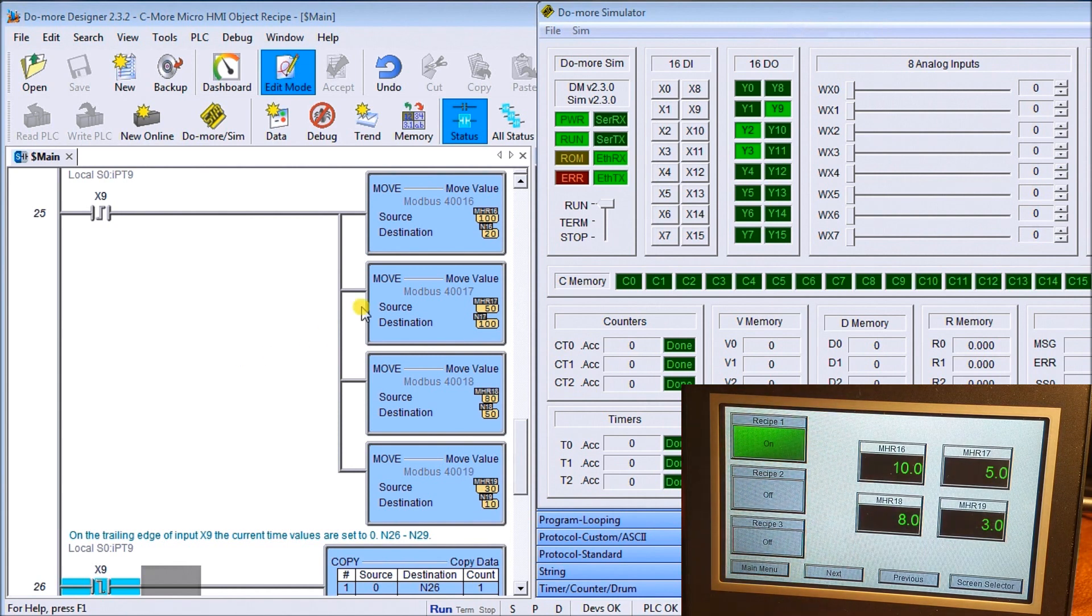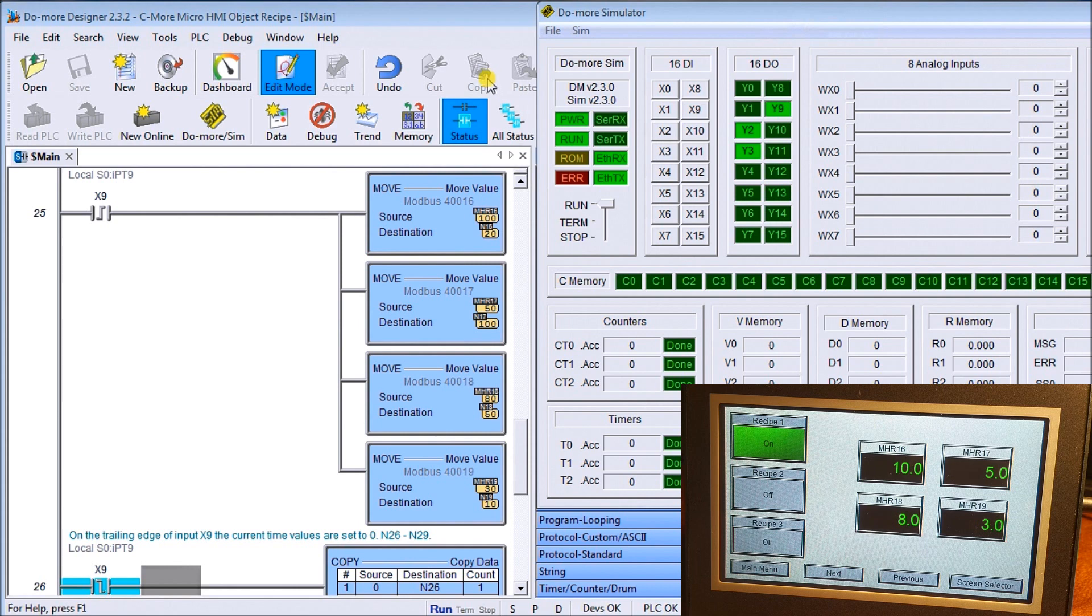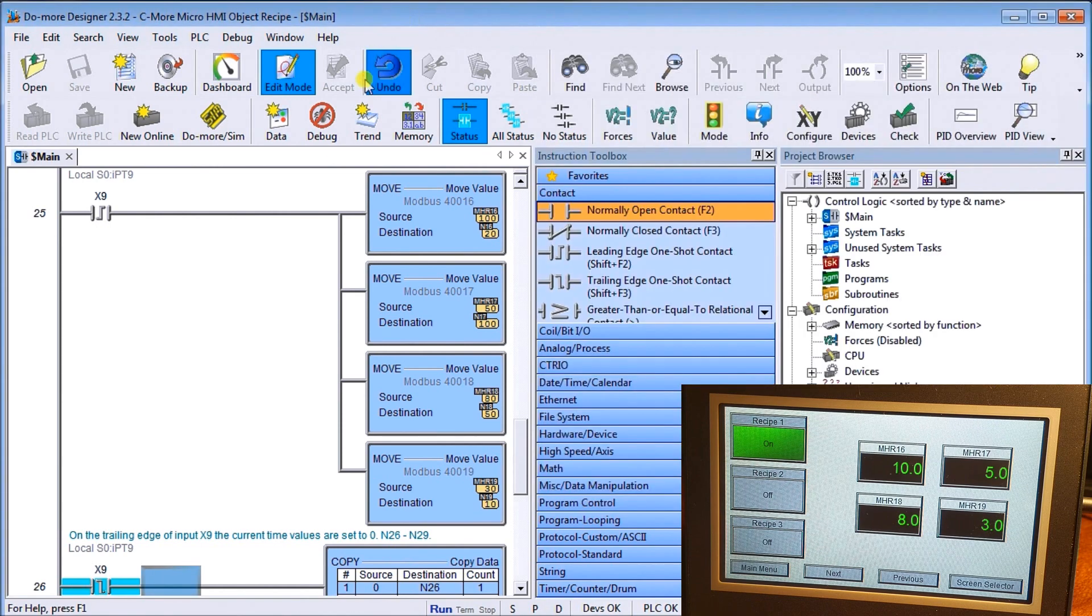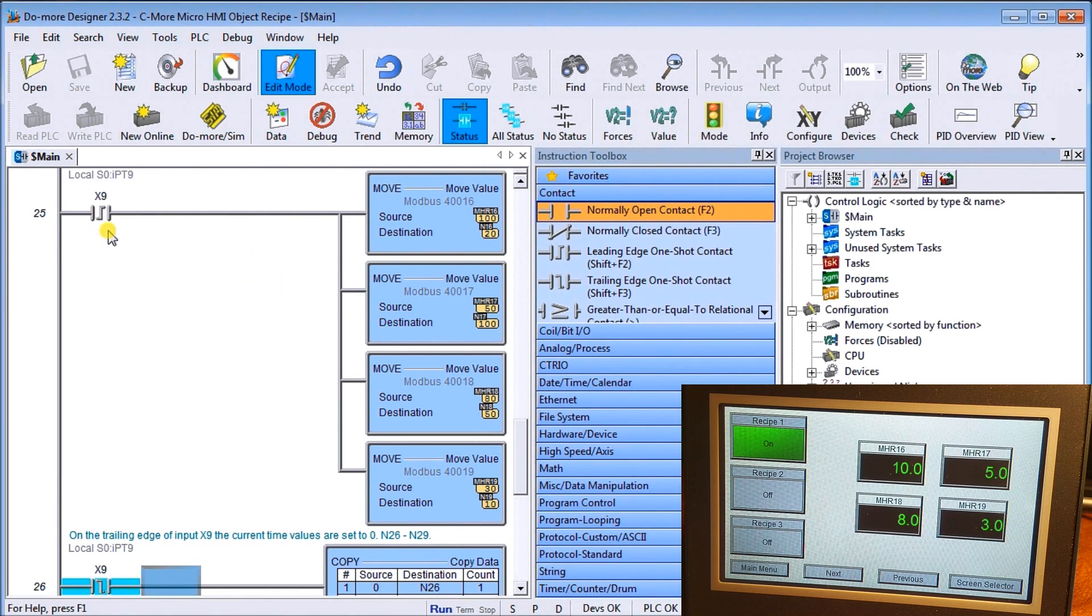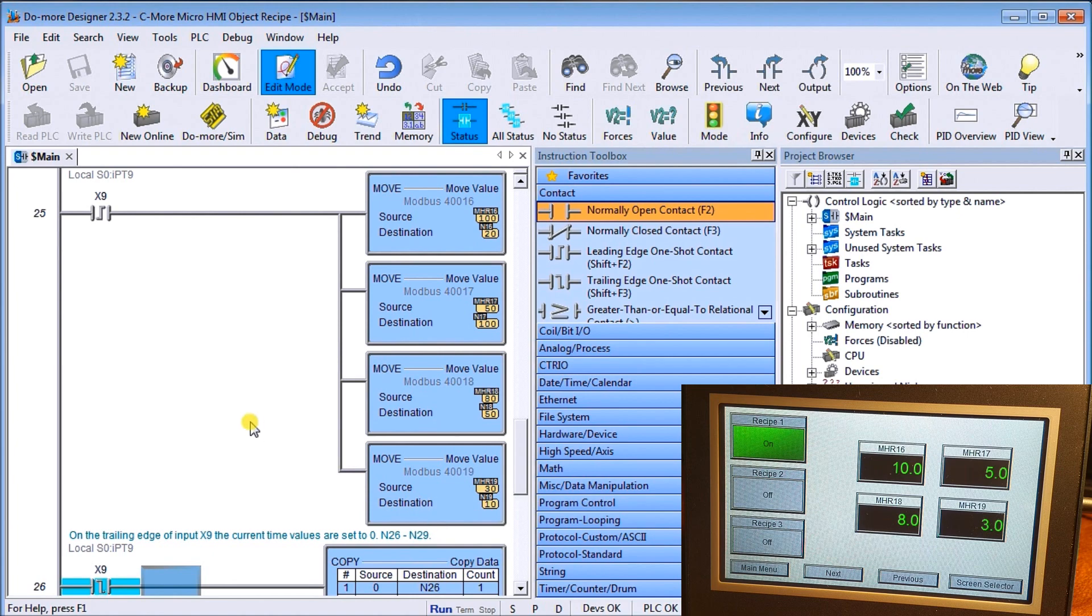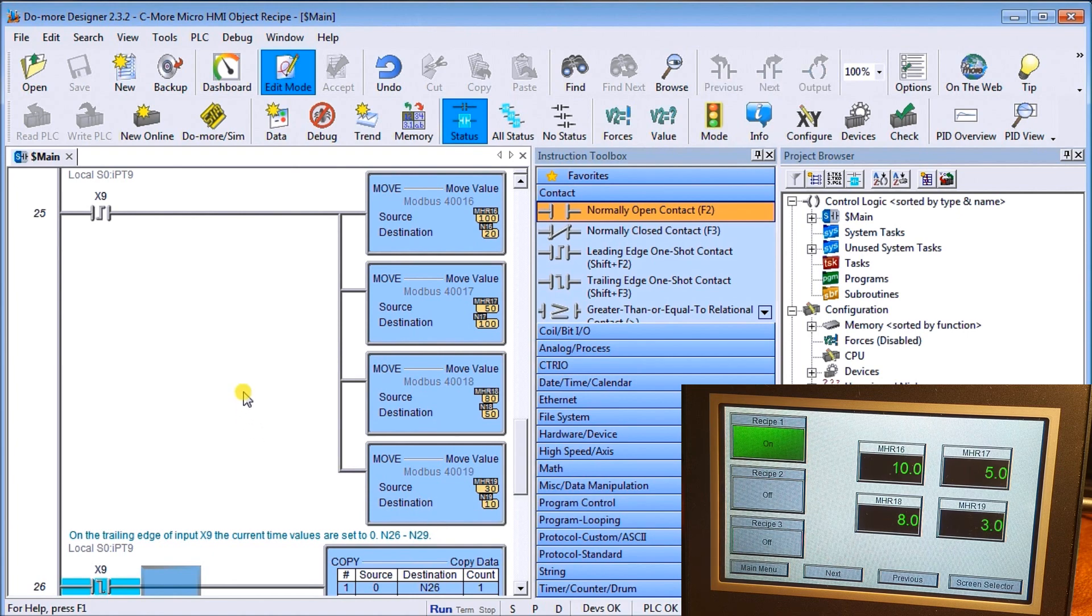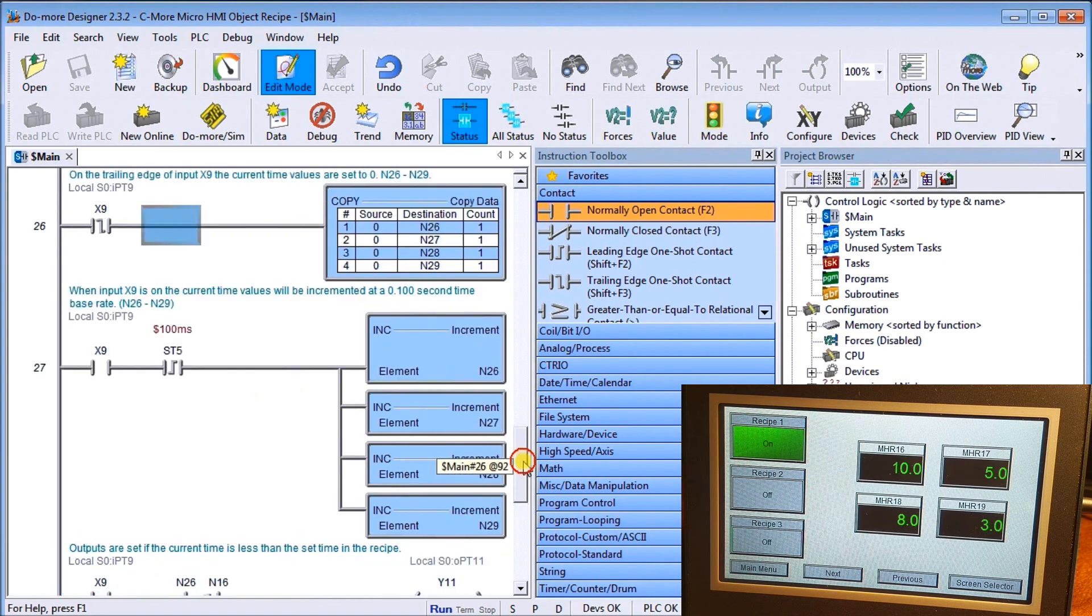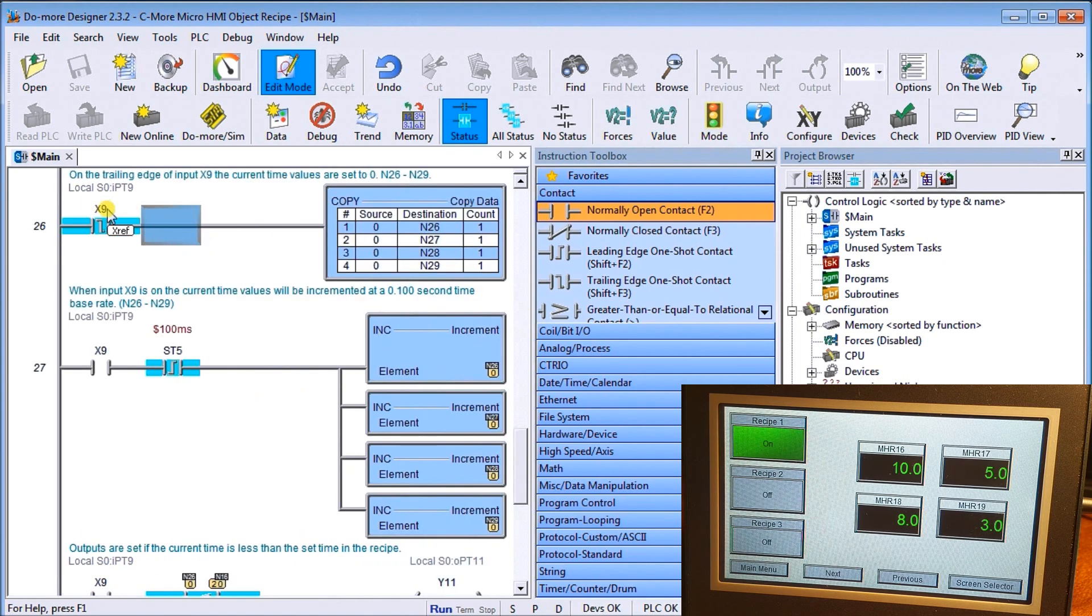Now if we look up on the screen, we're actually connected to our Do-more Designer and our Do-more simulator. Let's first of all look at the program. What we have is X9. When it first comes on, it will transfer MHR 16, 17, 18, and 19 into N 16, 17, 18, and 19. So that is our set value for our timers that we're going to be programming.